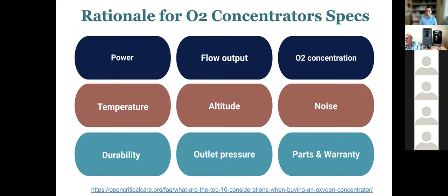Flow output, as mentioned before: most commonly concentrators are in the 0 to 5 liter per minute range, not infrequently up to 10 liters per minute. There are devices that can produce more than 10 liters per minute, but they're less common. A big thing to remember with flow output is the oxygen concentration. Many devices will claim they have high flow output, or even that their flow output is in the 5 range, but the concentration of oxygen at that max flow may be completely inadequate. Flow output in itself is not a good measure of whether this device is sufficient for my patients. What you really want is to make sure that the oxygen concentration at the max flow that the manufacturer is reporting is greater than 82%. In most devices, in most cases, it's going to be 90% or higher. So that's a big one to keep an eye on, and a common place where manufacturers, unfortunately, can be misleading in the advertisements for these devices.